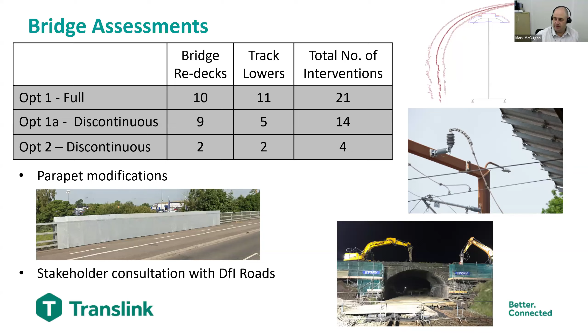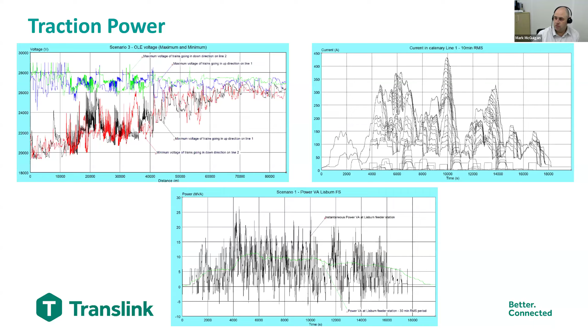Another key element is around the grid connections we require, and we've done quite a bit of traction power modelling. Although we say it's a 25,000 volt system, it isn't consistently so. We have trains on the network at all times, some accelerating and drawing more power than others coasting at line speed. When braking, we're regenerating energy and feeding it back into the system, so a lot of modelling is needed to ensure voltage and current remain within specific limits. We also look at how we could operate if we lose a substation, and we model for that as well.